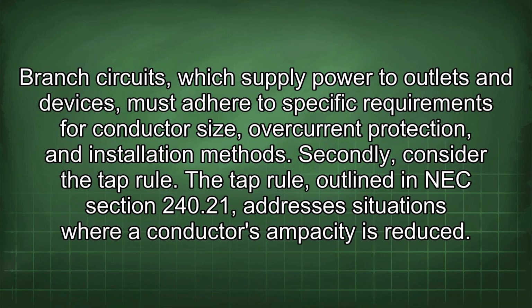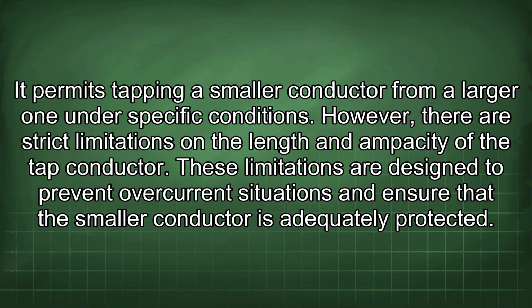The tap rule, outlined in NEC section 240.21, addresses situations where a conductor's ampacity is reduced. It permits tapping a smaller conductor from a larger one under specific conditions. However, there are strict limitations on the length and ampacity of the tap conductor. These limitations are designed to prevent overcurrent situations and ensure that the smaller conductor is adequately protected.